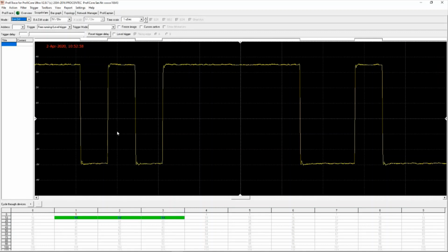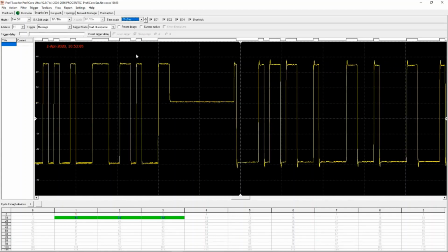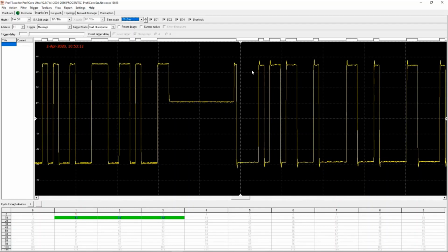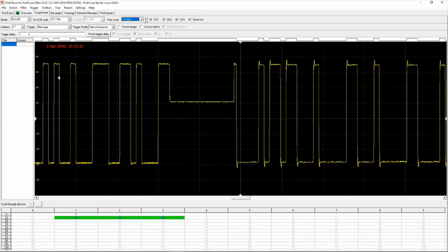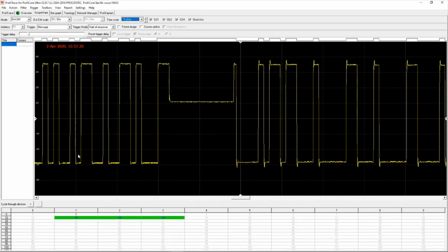When I mentioned that we use oscilloscopes to typically diagnose or look at the true health of a network, the scope which I'm showing you in front of you, this is actually the Profibus signal. This is the binary signal that is traveling through that copper cable, which has got the request from the controller, and then it's got the response from the slave device, which is traveling through. You expect to see this to be nice, square, and even.